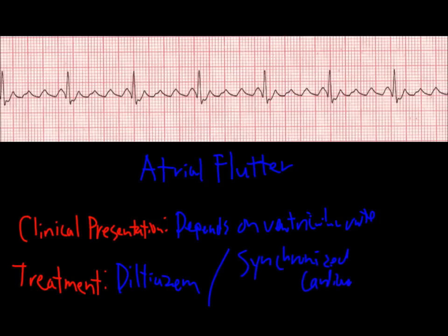Now, this is not the same thing as defibrillation or shocking a patient. The term shock can be used interchangeably with defibrillate, but you cannot use either one of those terms when you're talking about synchronized cardioversion. Synchronized cardioversion is when you're sending a controlled dose of electricity at a certain point in the cardiac cycle, usually right before ventricular contraction.